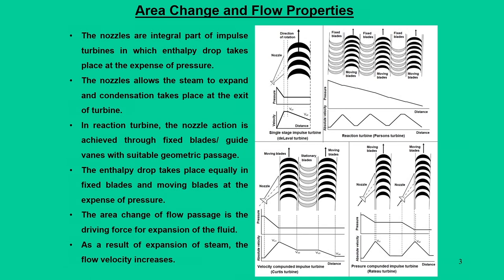What happens is that all the enthalpy drop — the total enthalpy of the steam — is compensated through the pressure drop. When you do this expansion in reaction turbines, although there is no separate component of nozzle as such, they have fixed blades or guide vanes that take care of the pressure drop. The passage of those fixed blades is such that they perform nozzle action: the flow has to expand, the velocity must increase, and pressure must drop. For impulse turbines nozzles are integral components; for reaction turbines nozzle action is achieved through fixed blade or guide vane arrangements.